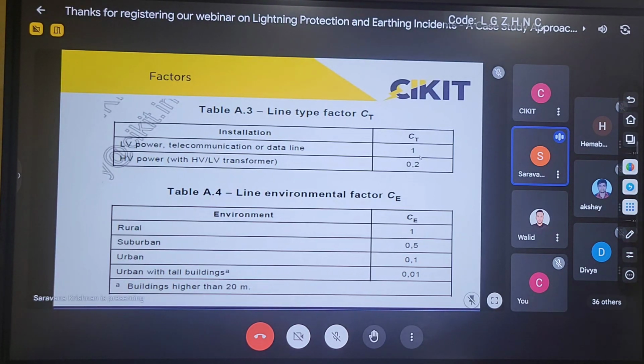So if lightning is striking any structure, and my building is located in a rural and isolated area, the entire surge will travel along the particular line, and the magnitude of surge entering my building will be higher, and hence the damage also will be higher. But if my building is located within city limits, in an urban area, and lightning strikes that particular line, there will be more parallel paths for the lightning. From the same line itself, almost 10 to 20 members will be taking power supply. So the surge's magnitude will be reduced, and the damage also will be reduced. That is the reason the risk varies based on the line environmental factor.